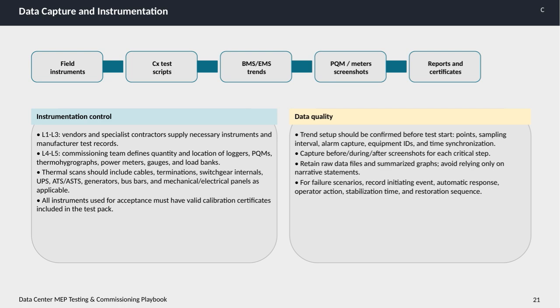It's essential to emphasize that every instrument used for acceptance testing must come with a valid calibration certificate, which must be included in the test documentation pack. Moving on to data quality. Before starting any test, it's crucial to confirm trend setup parameters such as data points, sampling intervals, alarm captures, equipment identification, and time synchronization to ensure accuracy.